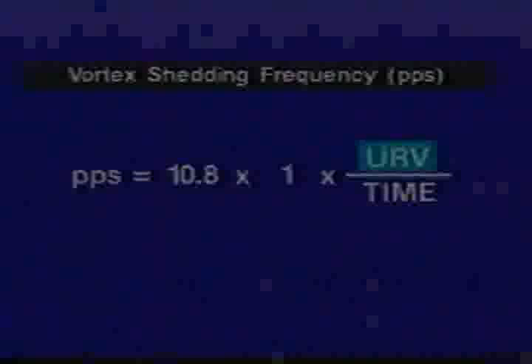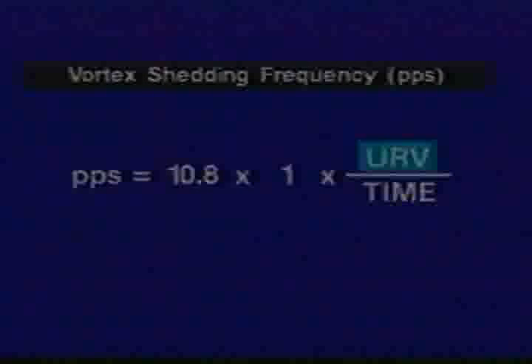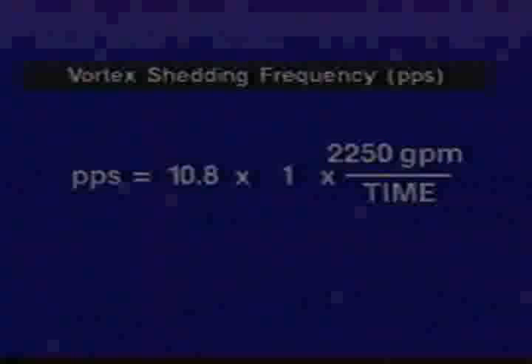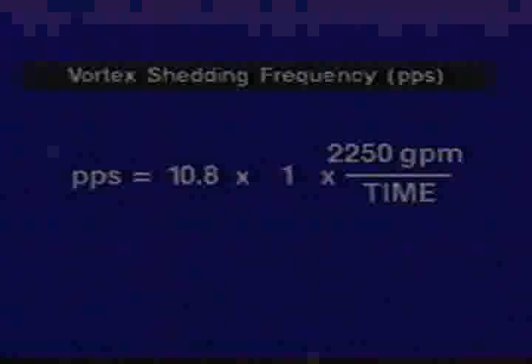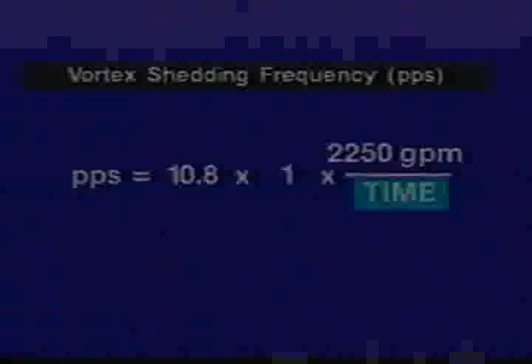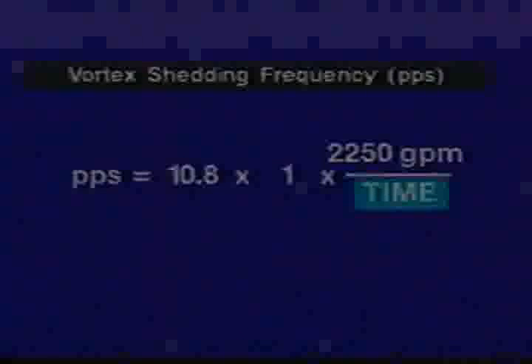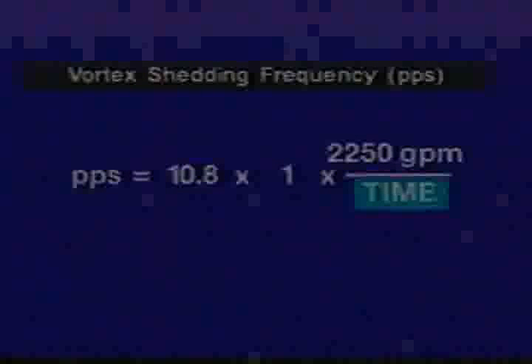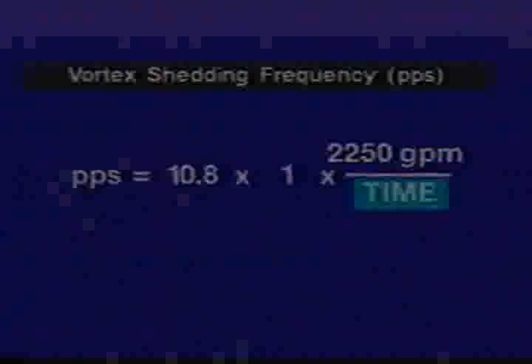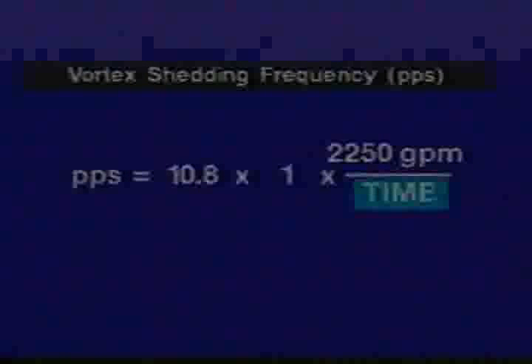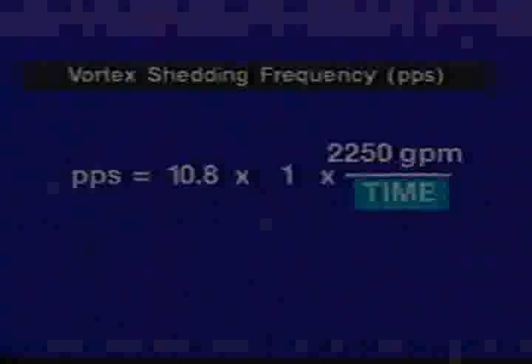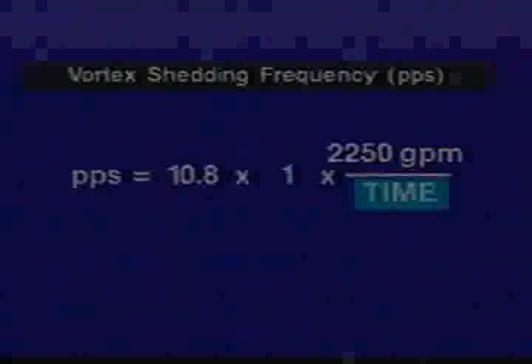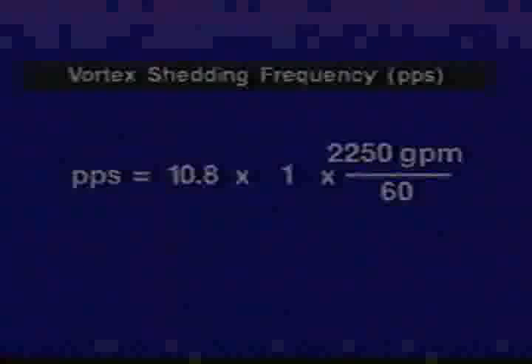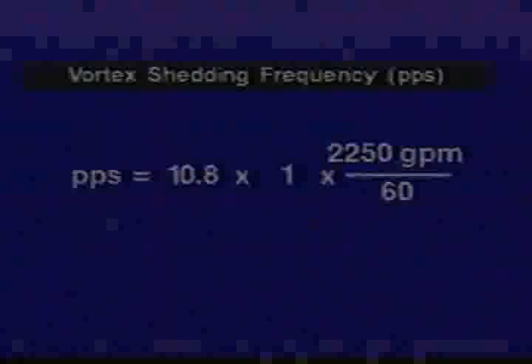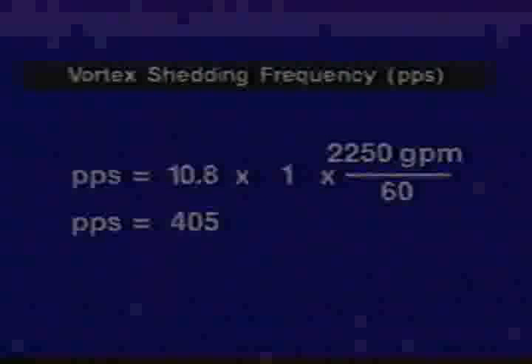URV is the upper range value in US gallons per minute. We can use a URV of 2,250 GPM here. And time is a value that depends on the increment of time in which flow is measured. A value of 1 represents 1 unit per second, so a value of 60 represents 1 unit per minute, and a value of 3,600 represents 1 unit per hour. Now we'll apply 60 as the time value in this calculation.